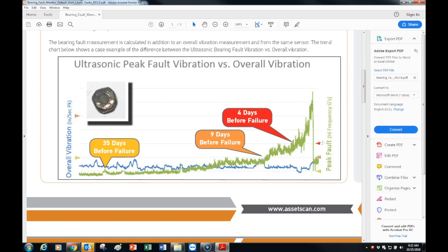This trend is a 30-day trend of a bearing, a bearing fault or bearing that came out of this machine. This is what one of the elements looked like. At this point obviously bearing was no longer rolling, it was sliding, it was grinding, it was setting off some smoke and sparks.